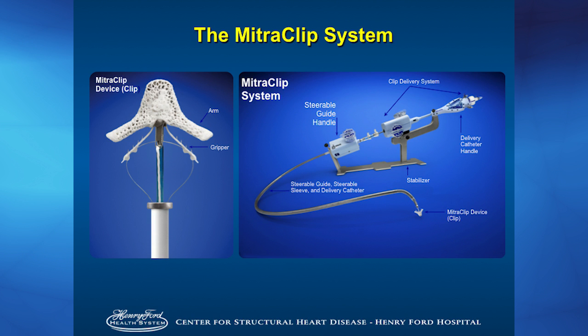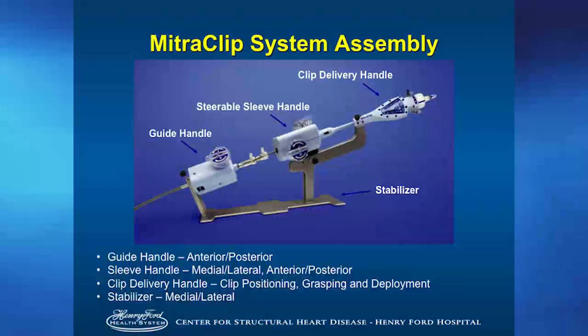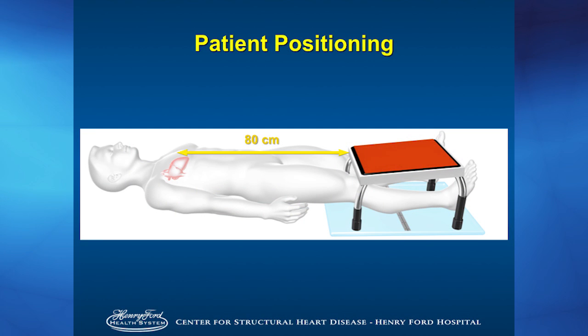No CT is needed for this. It's all intraprocedural TEE guidance. No actual contrast is needed for this procedure. It's just fluoroscopy and TEE with a good probe. This is an assembly system. There's knobs, there's hardware, it's huge. It goes from a venous access and goes to transeptal sheath delivery system. And this is how it's set up. There's actually a little assigned MitraClip stool that's given to the patient, and we put the device on top of that, and you have to have 80 centimeters to the chest wall for the atrium.